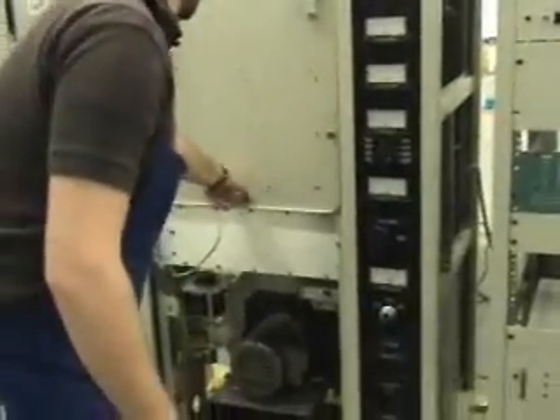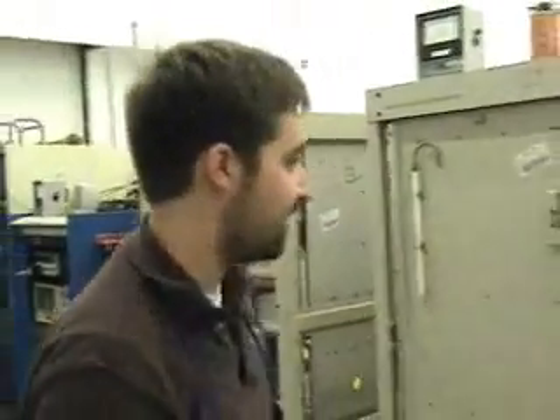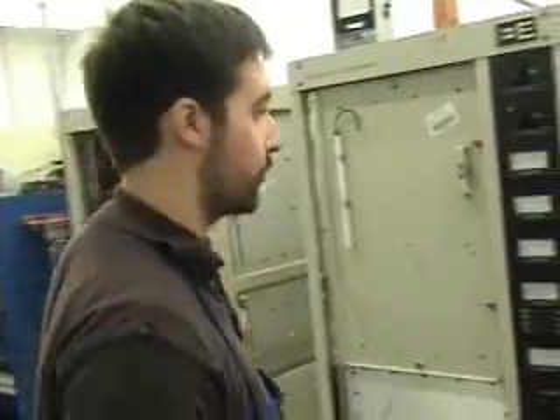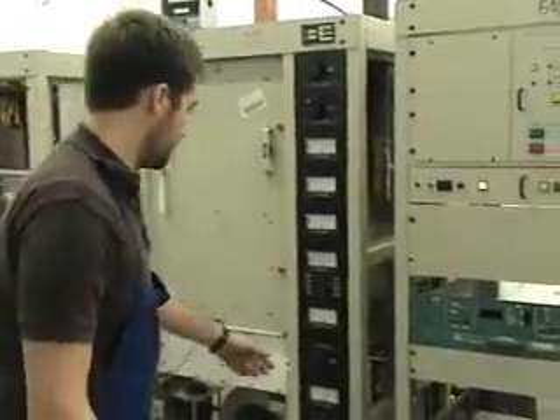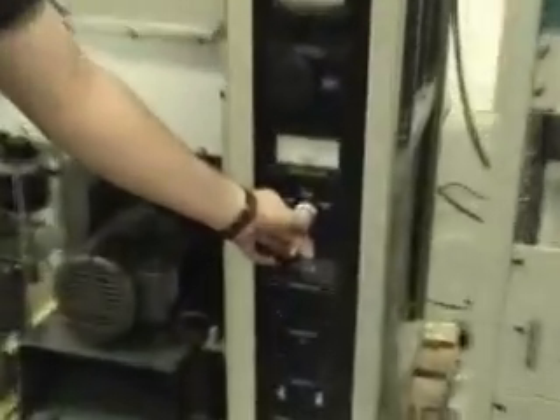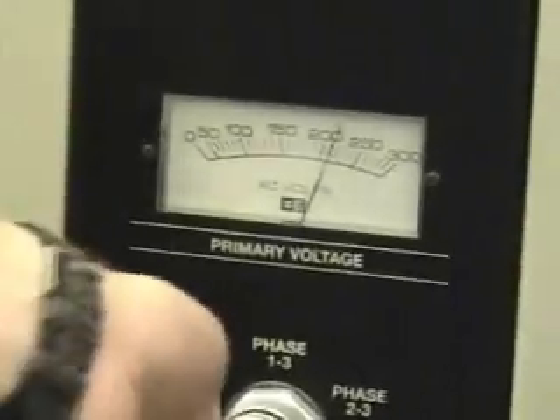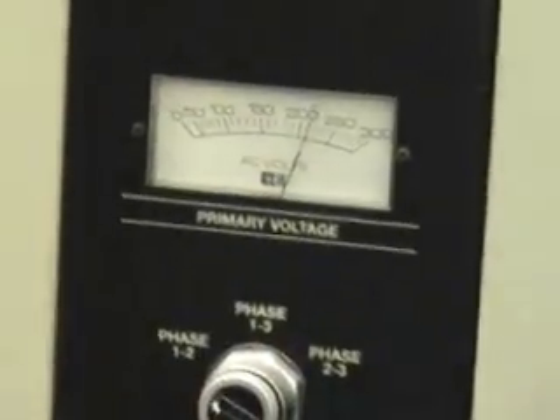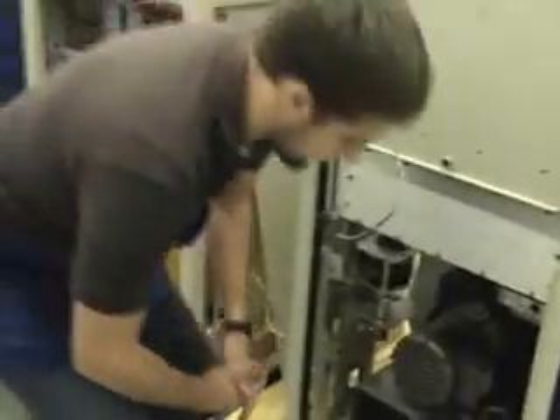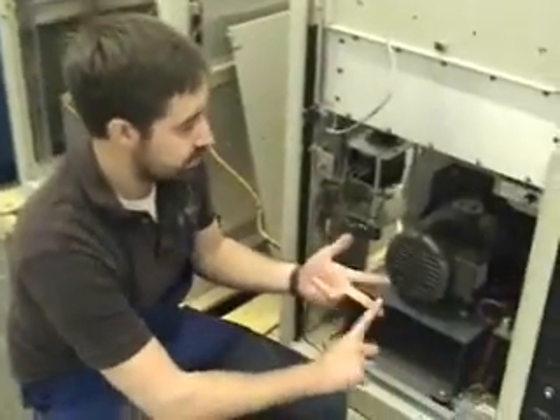Okay, like I said, make sure the high voltage is off because you don't want the transmitter coming up with high voltage initial turn on. We just want to make sure things are working in order. So right here in the front, you can check your voltage. Another thing you're going to want to look at, you won't even get an interlock light. It will not come up at all unless the phases are in order, 1, 2, 3.